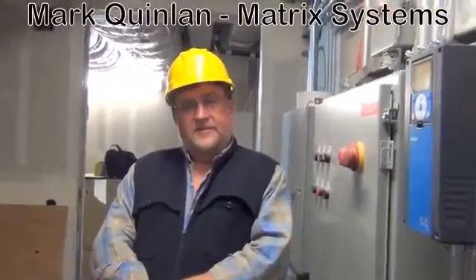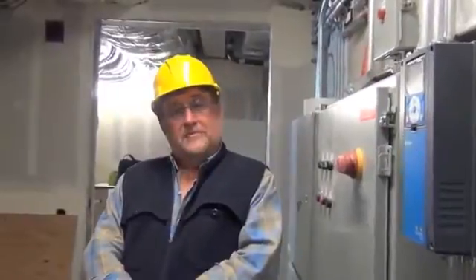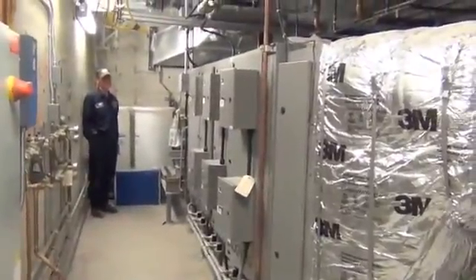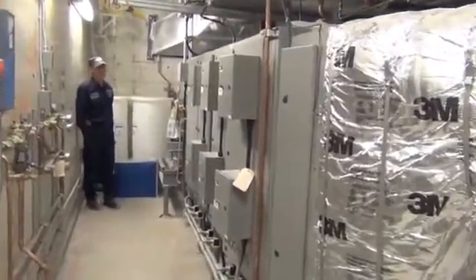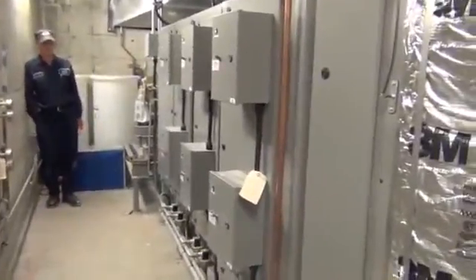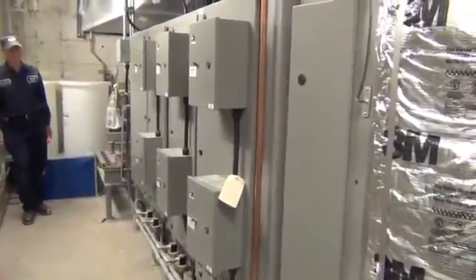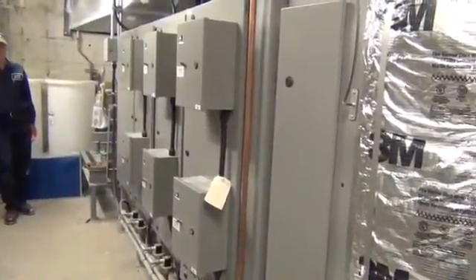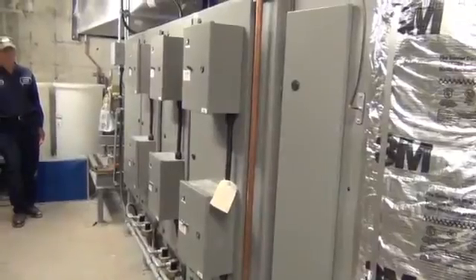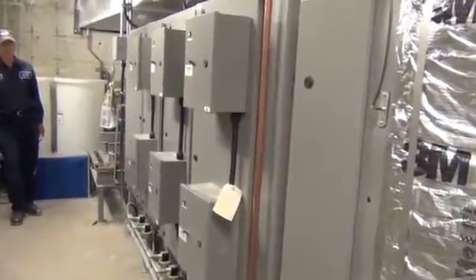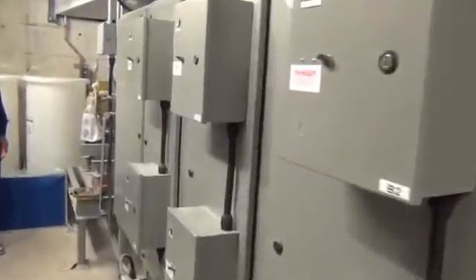We are the United Air Specialist Smog Hog Manufacturer Certified Sales and Service Agency for Northern California and Northern Nevada. We've recently installed 3 Smog Hogs to examine how Smog Hogs work and their common applications. This is a model PSG 22-3 Smog Hog from United Air Specialists with an airflow capacity of between 4,400 and 6,200 cubic feet per minute. It's used to filter grease, smoke, and odor from commercial kitchen exhaust. It's being used in a high-end Chinese restaurant in San Francisco.